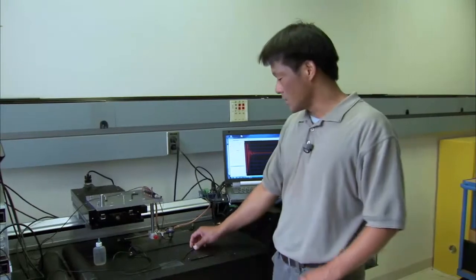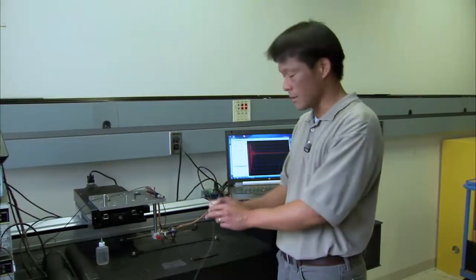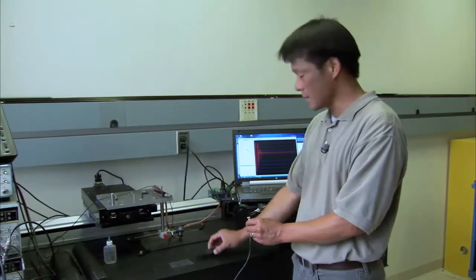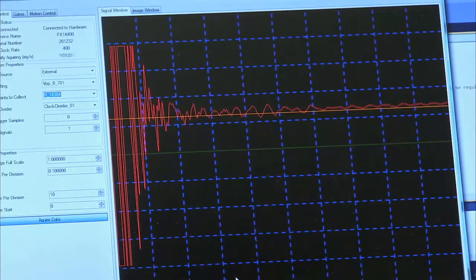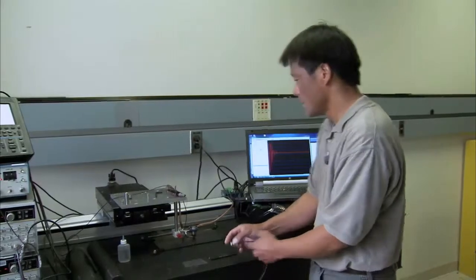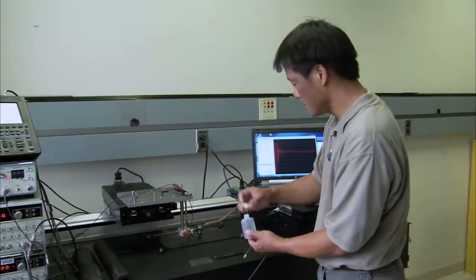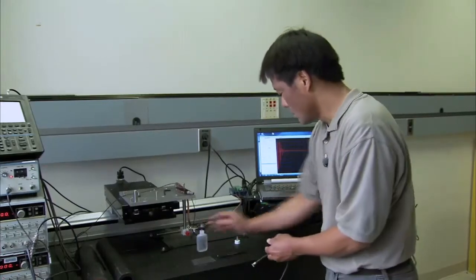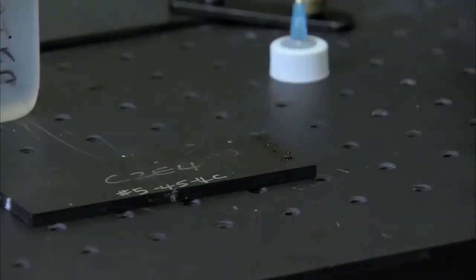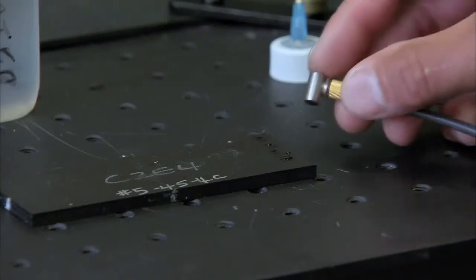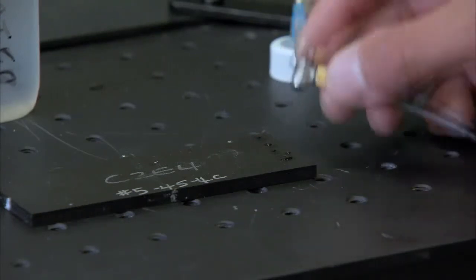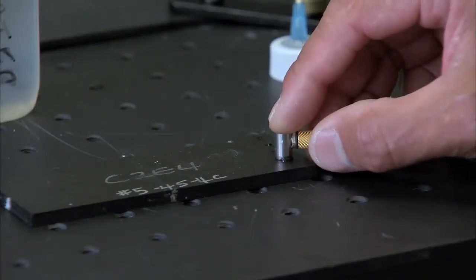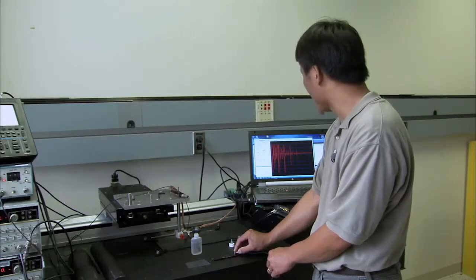Hi, let me demonstrate this technology to you. I have an ultrasonic transducer here, and I have a sample that I want to inspect. If I don't have any coupling medium, I push down on the sample, and you can see on the screen that there's no change in the ultrasonic waveform. A commonly used medium is water, so I'll just put a little water on the surface. And as you can see, as I press down, the waveform changes, showing that the ultrasonic energy is transferring into the sample and reflecting back through the sample.